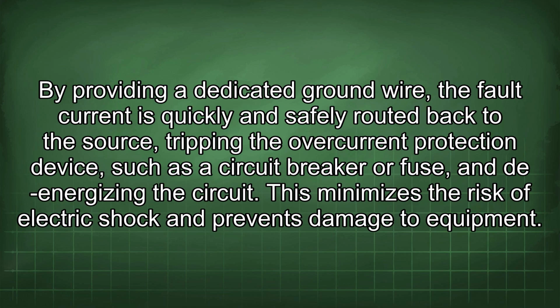By providing a dedicated ground wire, the fault current is quickly and safely routed back to the source, tripping the overcurrent protection device such as a circuit breaker or fuse, and de-energizing the circuit. This minimizes the risk of electric shock and prevents damage to equipment.